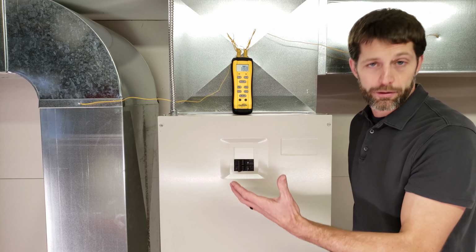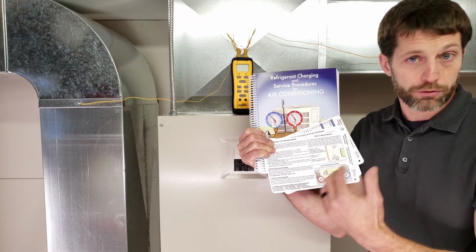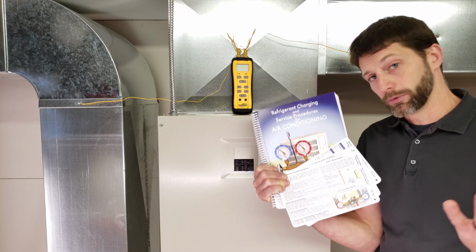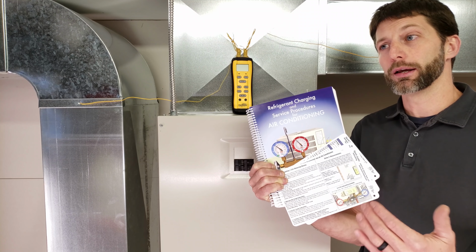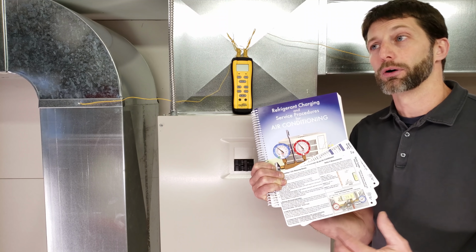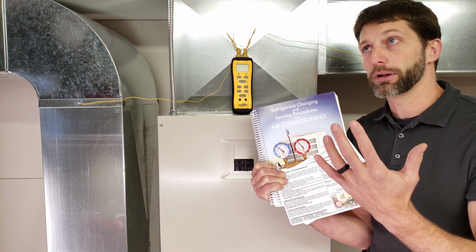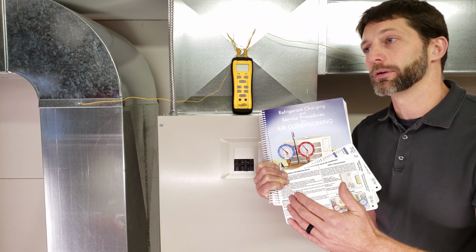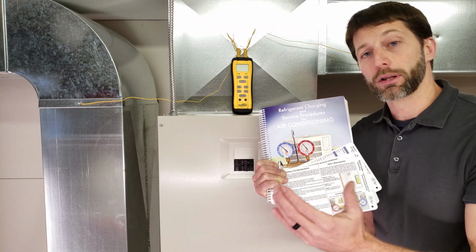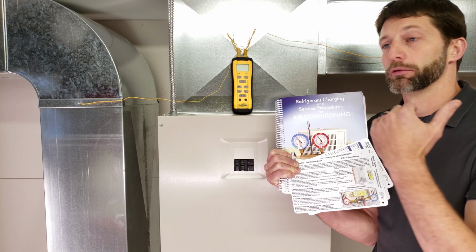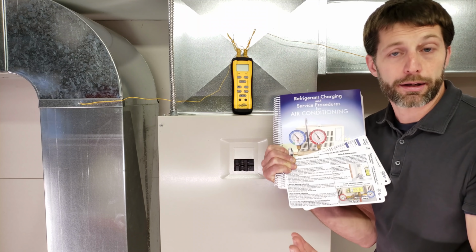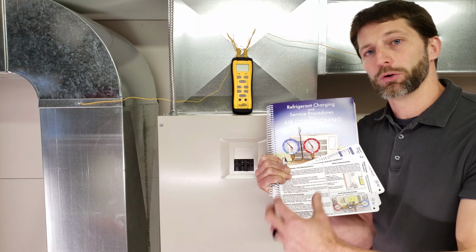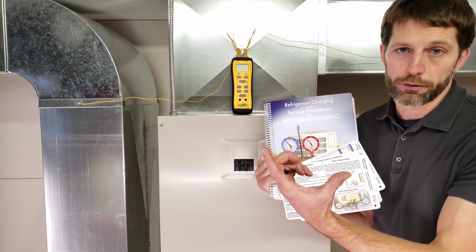But over here on our Delta T, we have a couple notes just to remind you. If you have a lower than 18 degree Delta T, it could be a low refrigerant charge, but it could also be that you have high humidity in the building. So you could have a high heat load in the building, and remember that a fixed orifice can't let more refrigerant into a system in order to handle a higher heat load like a TXV can. So even though your refrigerant charge is good, you may just have an extremely high heat load, and you just don't have enough saturated refrigerant in that evaporator coil to absorb that amount of heat. So you have a high superheat.